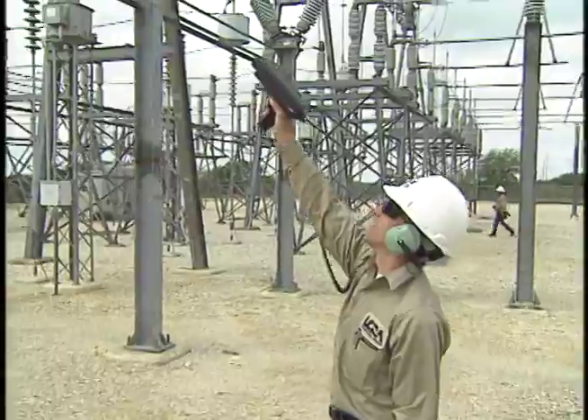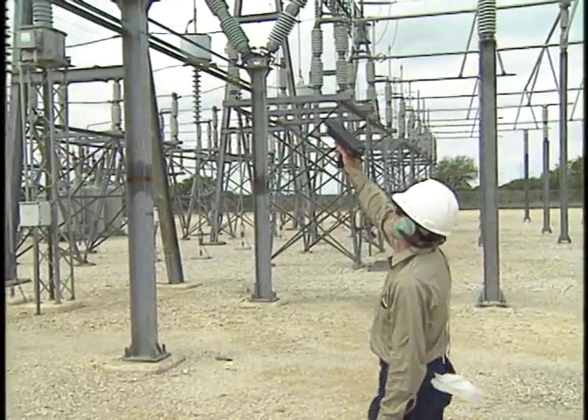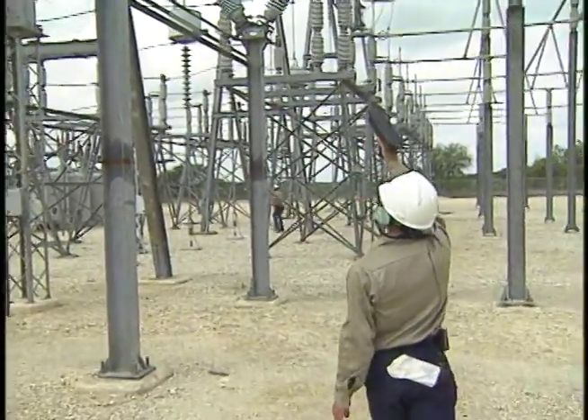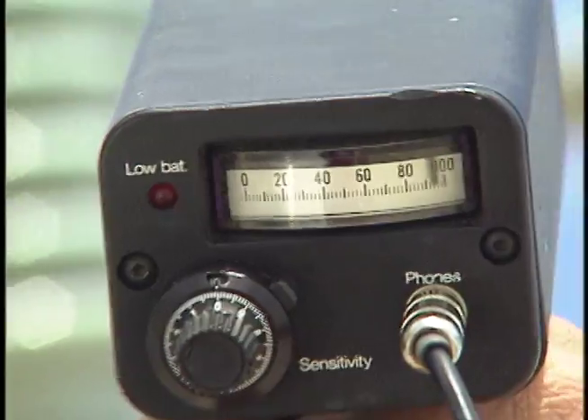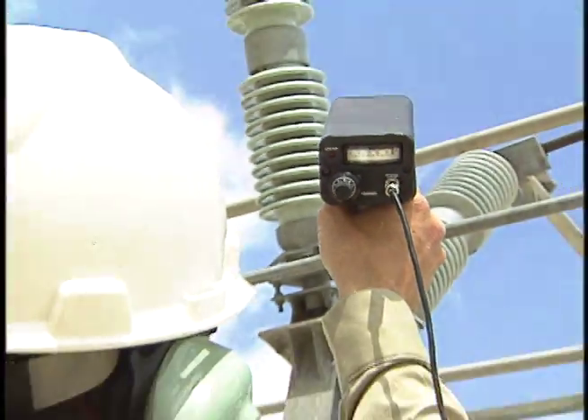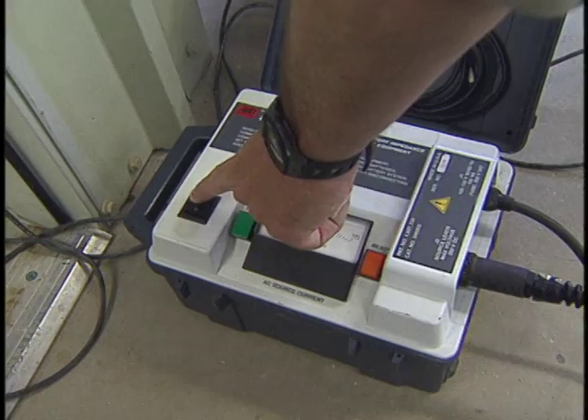The substation survey also includes listening for unusual sounds with this handheld microphone. A sound like this can indicate a loose connection, which can lead to trouble.